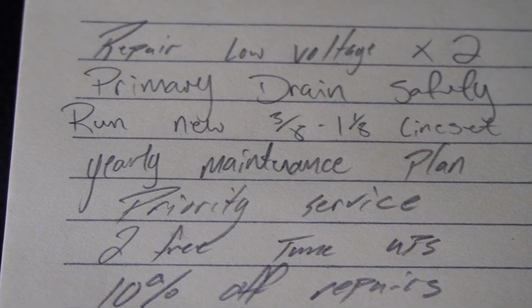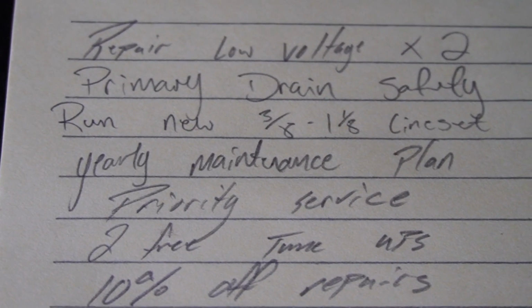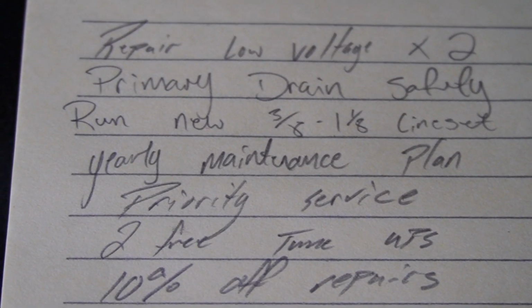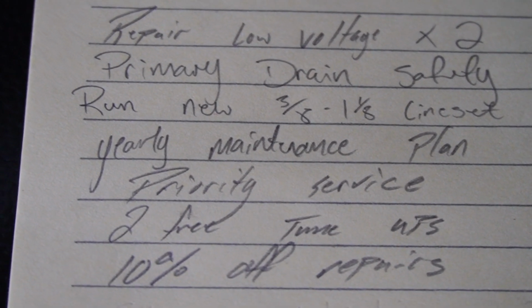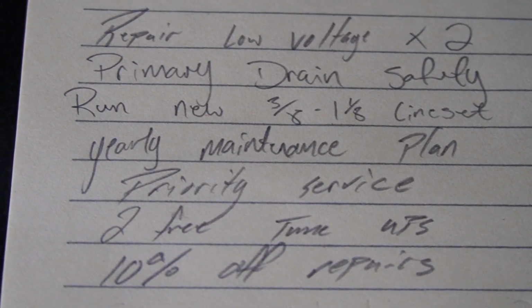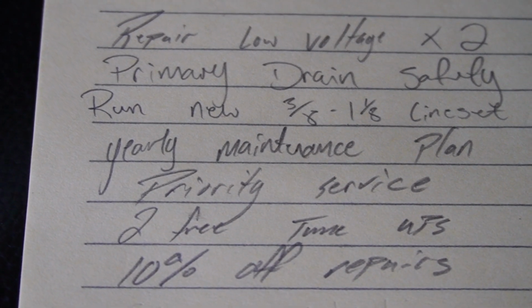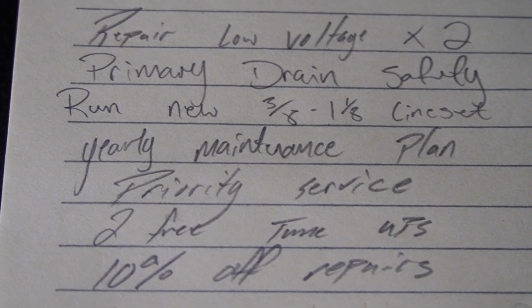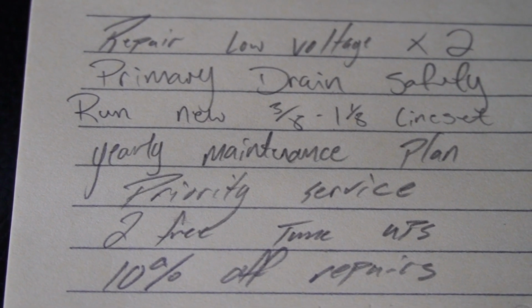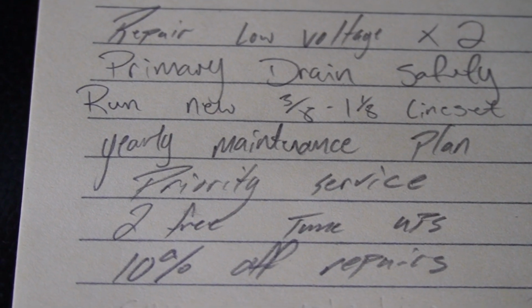Bird gang, so option sheet on what we've got so far here. We got two low voltage repairs because we have to correct wiring between the thermostat, air handler, and the outdoor unit. And then also correct the heat kit, that's got to come down to 10 kW, which is all it really needs.